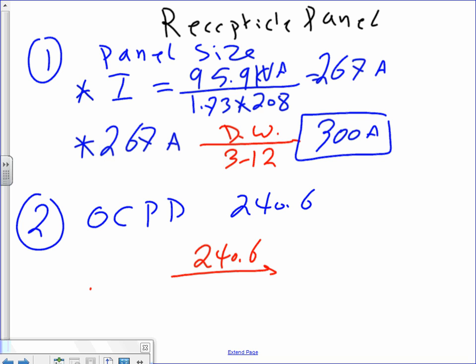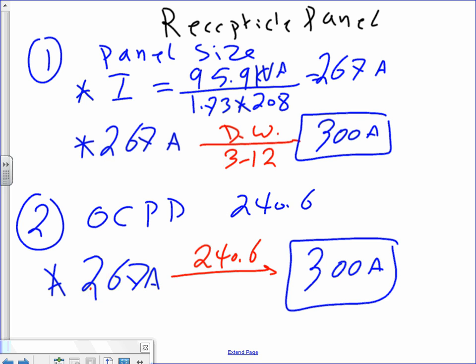All right, gentlemen. Overcurrent protection device. You go to 240. The same thing. You take the 267 amps, take it to 240.6, and if you go there, it will tell you, by the way, they also don't make it. You have to go to 300 amp. So now my panel and my overcurrent protection device match. Now, could it be that this will be 250 and the panel will be 300? Yes. So when you get into a situation like this, try to match the panel. It's a good idea to match your panels, if you can. Okay, so 300. Questions?